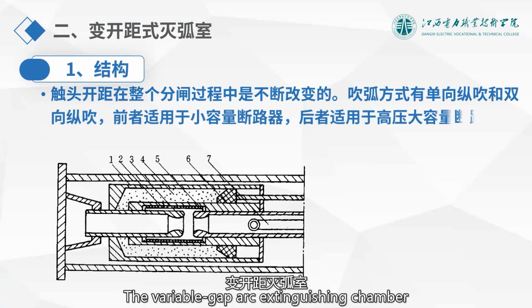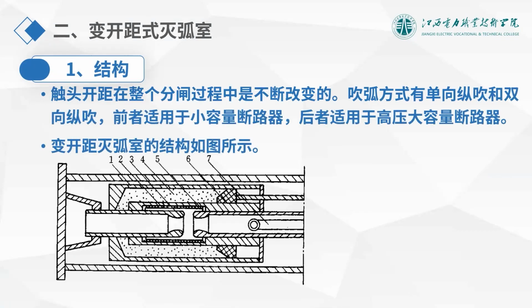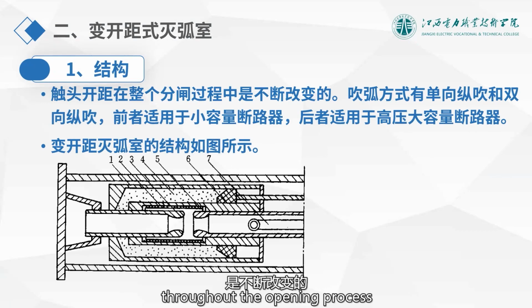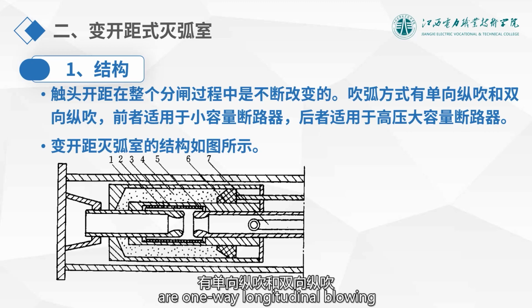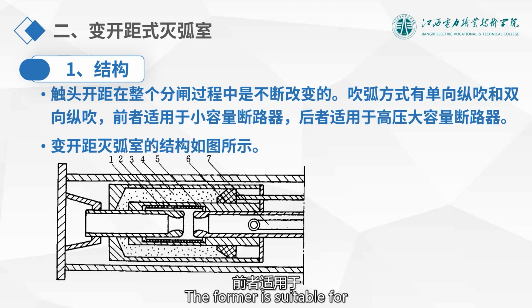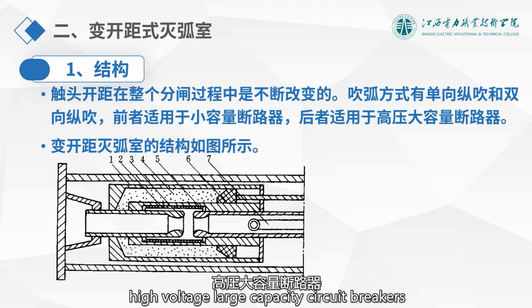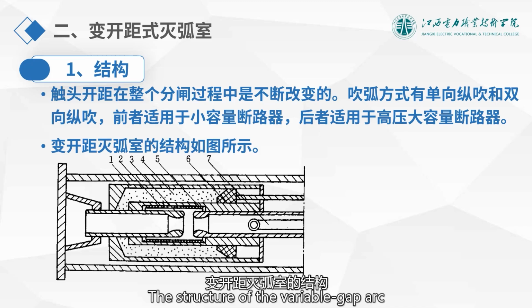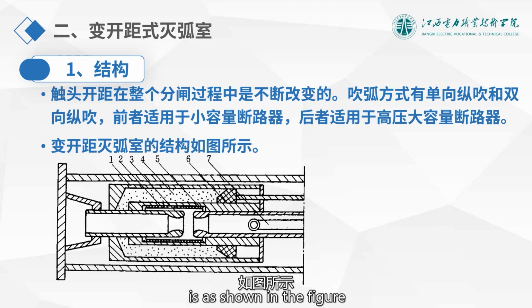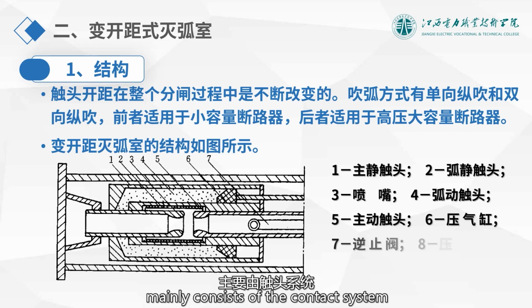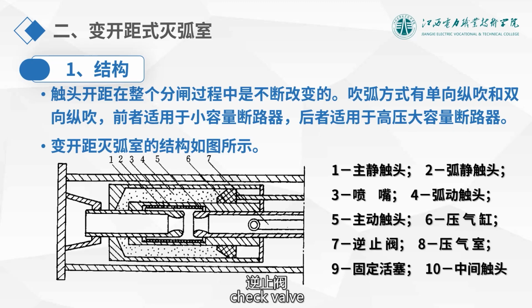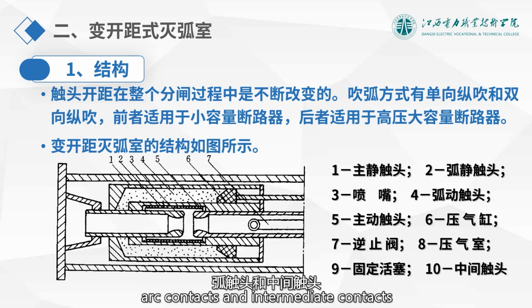The variable gap arc extinguishing chamber has a contact gap that continuously changes throughout the opening process. The arc blowing methods are one-way longitudinal blowing and two-way longitudinal blowing. The former is suitable for small capacity circuit breakers. The latter is suitable for high voltage large capacity circuit breakers. The structure of the variable gap arc extinguishing chamber is as shown in the figure. It mainly consists of the contact system, compression cylinder, check valve, compression chamber, and fixed piston. The contact system includes working contacts, arc contacts, and intermediate contacts.